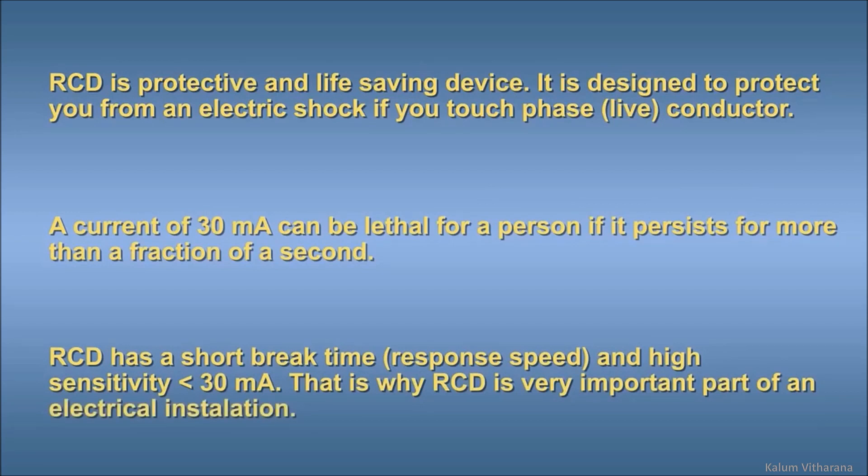A current of 30 milliamps can be lethal for a person if it persists for more than a fraction of a second. RCDs have short break time, fast response speed, and high sensitivity of less than 30 milliamps. That is why an RCD is a very important part of an electrical installation.